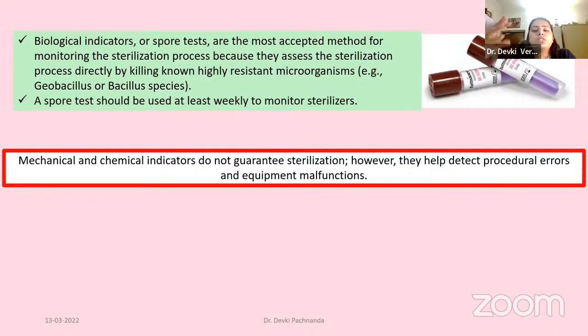Now, if you see these tubes, the basic principle behind them is, if the sterilization process has happened adequately, then the spore, which is resistant, is dead. So when you try to regrow it, you will not be able to obtain it. However, if the sterilization process did not happen adequately, you can grow the Bacillus, and when the Bacillus starts multiplying, there will be a change in pH, and the tube will turn from purple to yellow. Mechanical and chemical indicators do not guarantee your sterilization as a process, but they detect procedural errors and equipment malfunctions. The biological indicator will take 24 to 48 hours to know the report.